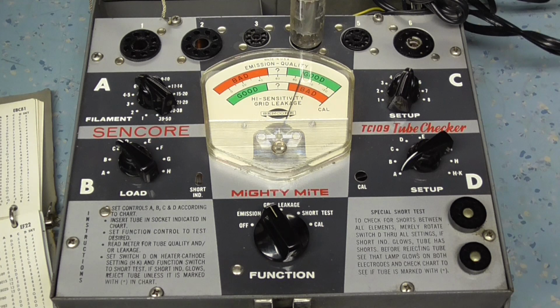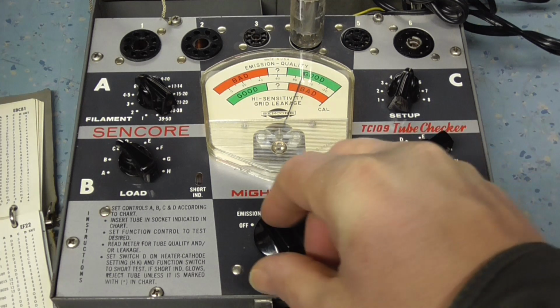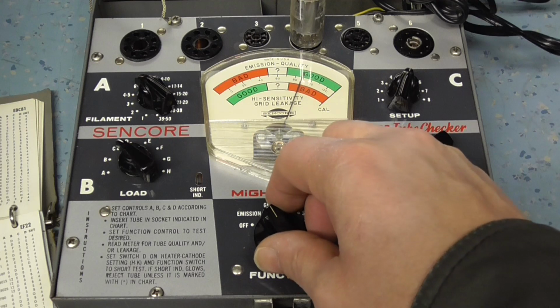I'm not going to bother checking the rectifier valve. We've proven that the HT comes up fine. There's no problem with any of the supplies, so that's good, isn't it? Currently testing 90%. I'm happy with that. That proves that that valve is good. So let's move on to the next valve, and hopefully that's the same.